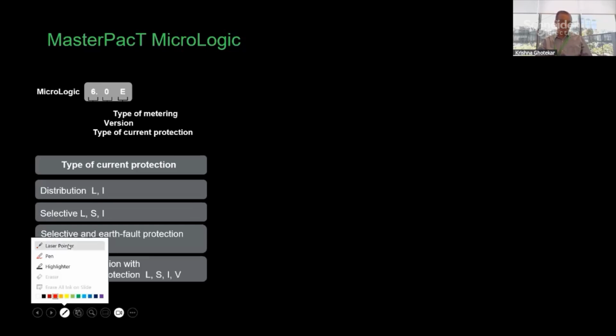In terms of trip unit, today the nomenclature for the trip unit is based on 2 parameters. One is the protection type. If you are familiar with our ACBs or MCCBs products, the nomenclature starts with 2, 5, 6 or 7. So 2, as a reminder, is overload and short circuit, but on short circuit, the time delay is fixed. The TSD is fixed. Then we have 5, which is LSI, overload, short circuit. All current and time is adjustable, and for instantaneous only current is adjustable. And 6 is LSIG. All current and time delay is adjustable for all except the instantaneous protection.